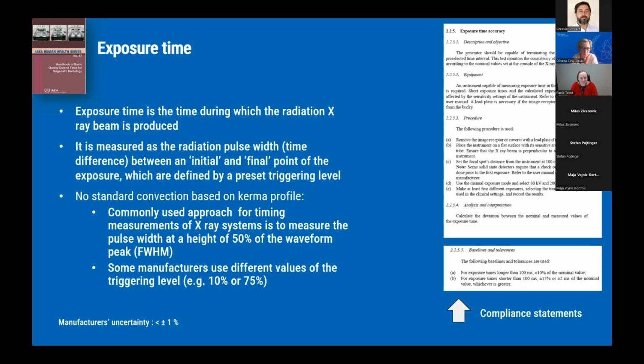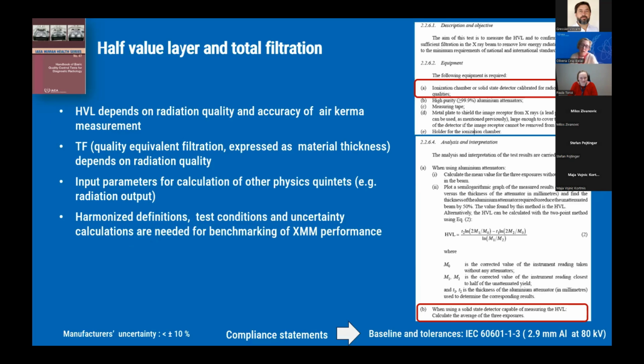In most of the manufacturer specifications, the accuracy of exposure time measurements would be better than 1%. But again, as clinical medical physicists, we have to provide a compliance statement that exposure time is better than 10 or 15% compared to the nominal one. And again, this compliance statement should be based on measurements that are associated with a certain uncertainty that needs to be assessed. And finally, about half-value layer and total filtration.